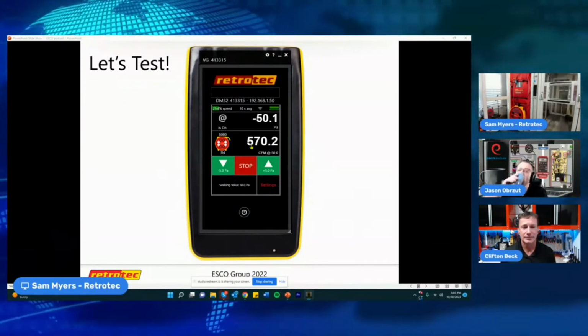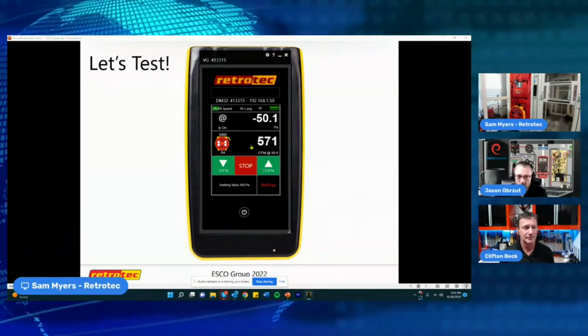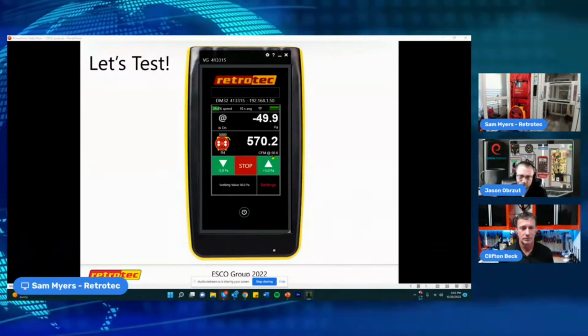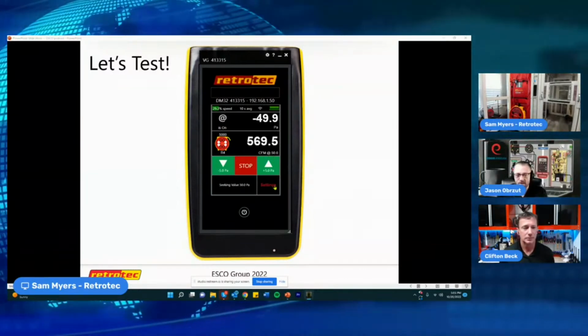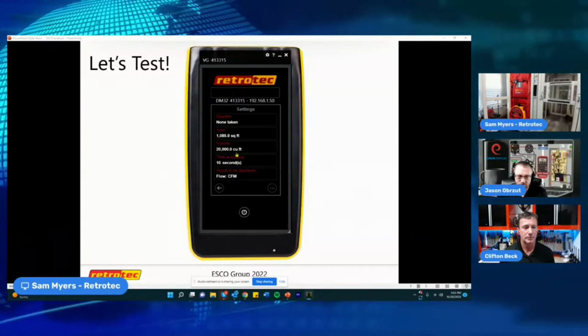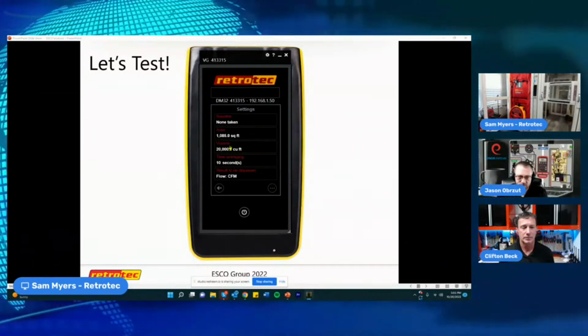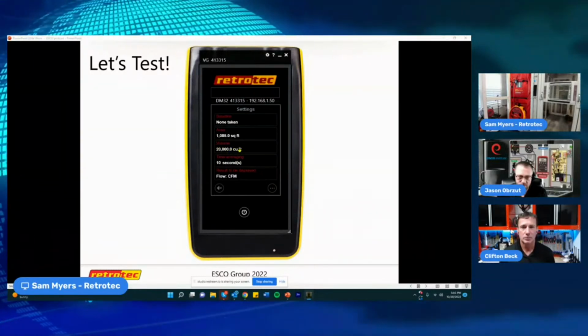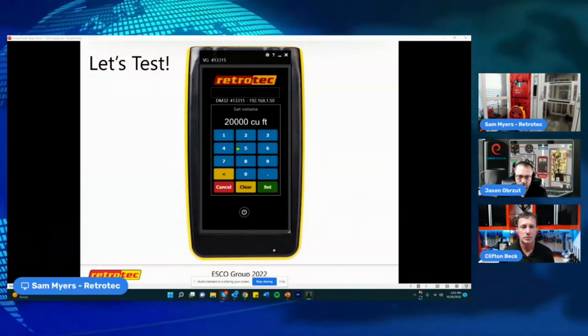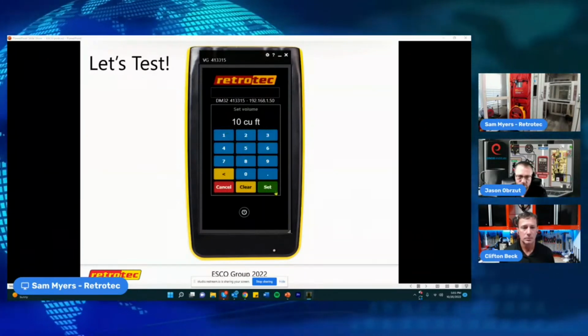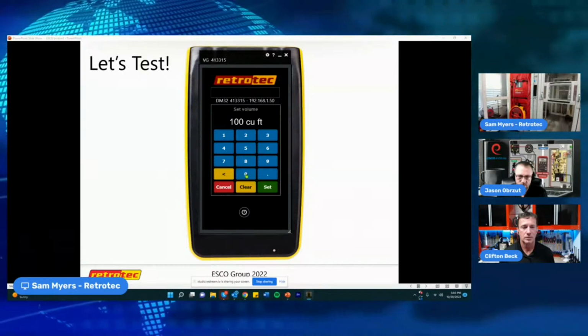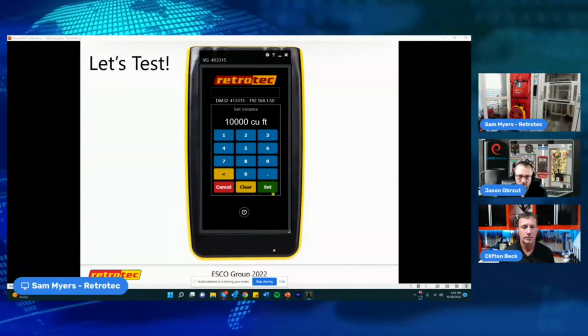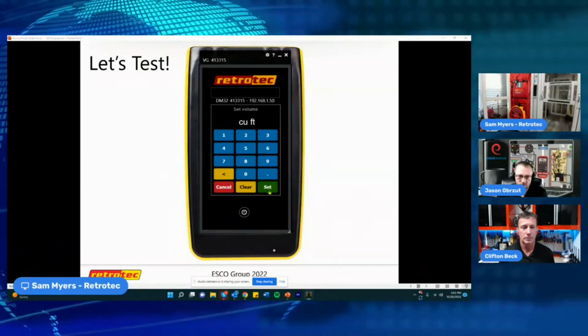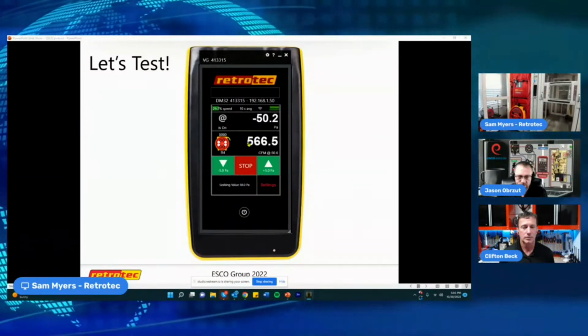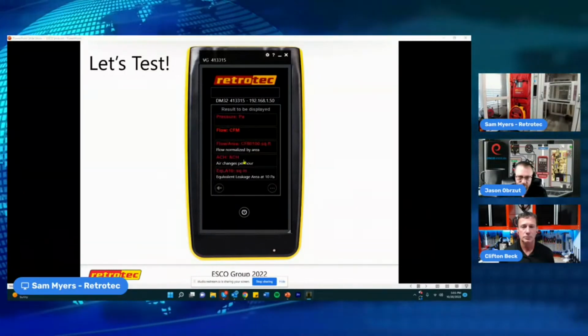So right here we're seeing about 570 CFM at 50. So we can see CFM at 50, and if I wanted to, I could go into my settings. Let's say our building was 20,000 cubic feet, we can change that too. We're testing a pretty small space here, so we'll just say 10,000 and hit set. Then I can go back in and choose ACH.